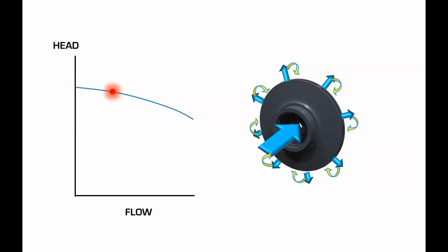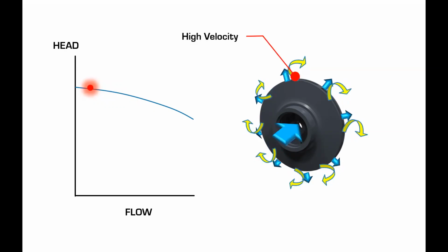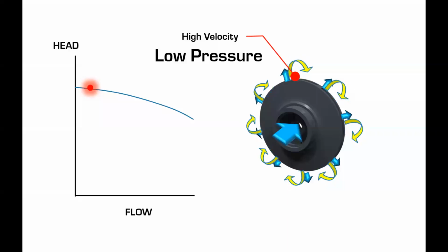Exactly. If we keep pushing this, that turbulence gets extremely high, and it gets so high that we get low pressure. We've said it many times in other webinars, Bernoulli's principle: as velocity goes up, pressure comes down. And it can come down so much that in a small localized area we're going to vaporize that fluid. Once that fluid vaporizes, it moves to an area maybe a millimeter away where it hits high pressure and it collapses in on itself.